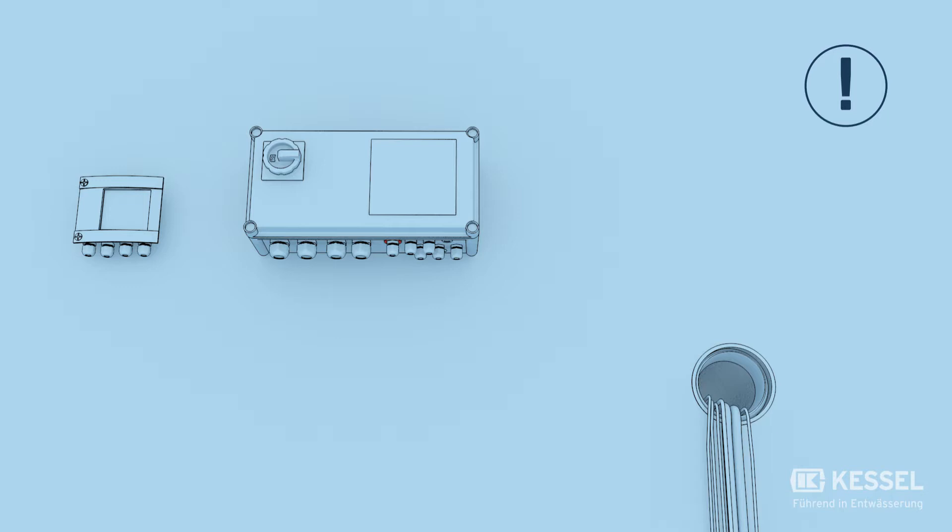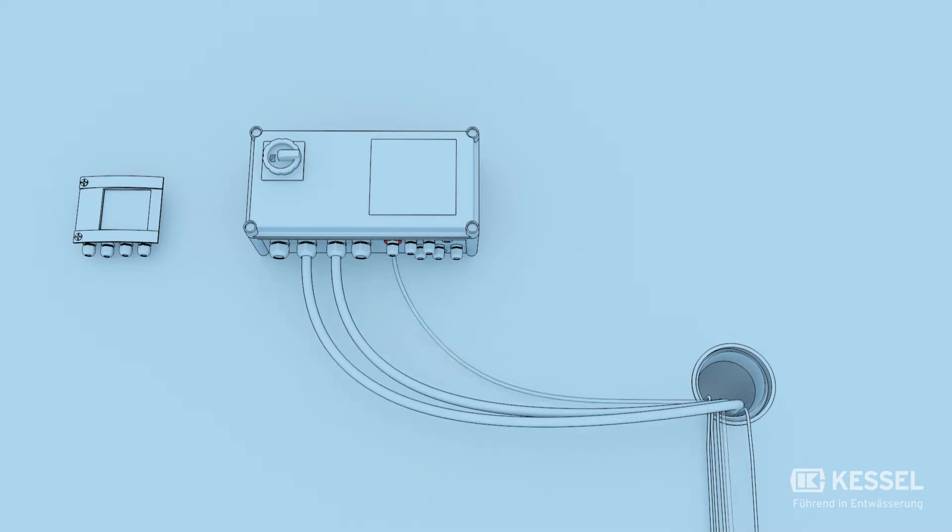Attention! Any of the following work may only be carried out by electricians with the required qualifications. First we connect the pump cables to the Comfort Plus main switch. Then we connect the pressure hose to the main switching device. Now we connect the signal line of the red alarm probe to the main switching device and mark the connection with a red flag. Now we connect the control line of the motor for the backflow valve to the main switching device.